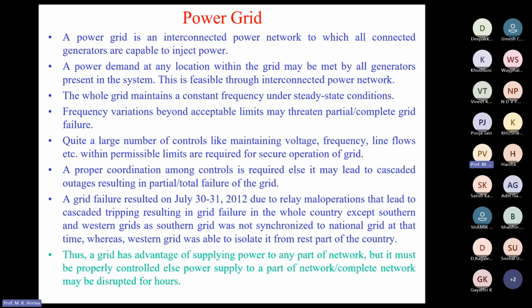A great example is the grid failure that happened on July 30th and 31st, and that happened due to relay maloperations. We have a protective system with different relays, but if there is no proper coordination among them, that may create problems. So there must be proper synchronization of all the equipment, and they must coordinate with respect to each other. The grid has the advantage of supplying power to any part of the network from any remote area, but it must be properly controlled. Else, it may cause failure or disruption of supply even for hours.